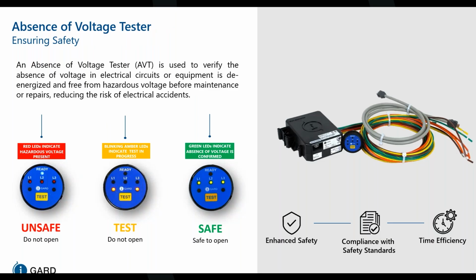Using an AVT is simple. A person can press the test button to initiate the test sequence. AVTs automatically self-test using a known voltage source and check for direct contact with the circuit during testing for both AC and DC voltages, including phase to ground and phase to phase. If the test is successful and there is less than 3 volts AC or DC in the circuits, 3 green lights will glow for 5 seconds. This indicates the situation is safe and the electrical panel door can be opened. In case of an unsuccessful test, either 3 red LEDs will glow, confirming the presence of voltage, or the amber lights stay illuminated, indicating a potentially unsafe condition.